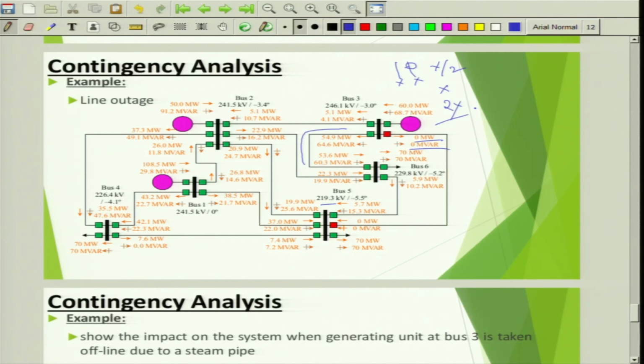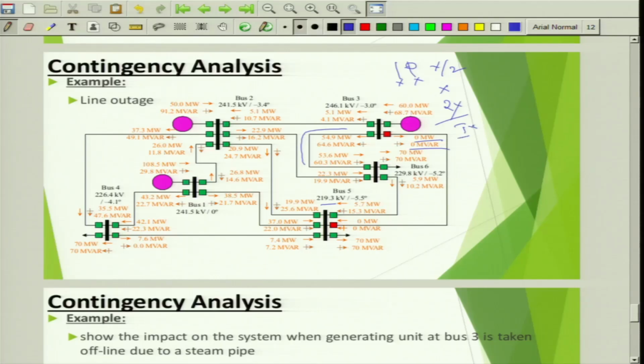The current is also increased. That means there is a doubling in the effect of reactance, impedance, as well as the current also. So the IR drop or IX drop will increase. Because of the increase in drop, there is a decrease in voltage at the receiving end, from bus 3 to bus 5, and this may lead to violation of the voltage limits. You understand, na? The effect of the line outage on the voltage limits. So this is one typical example.